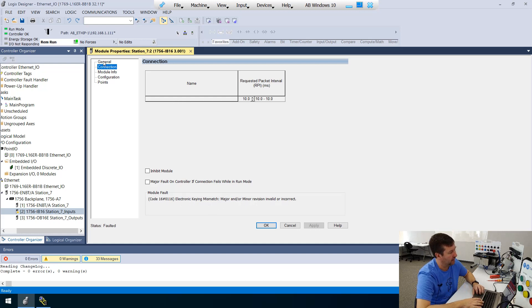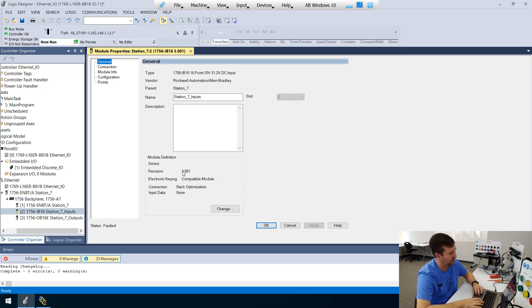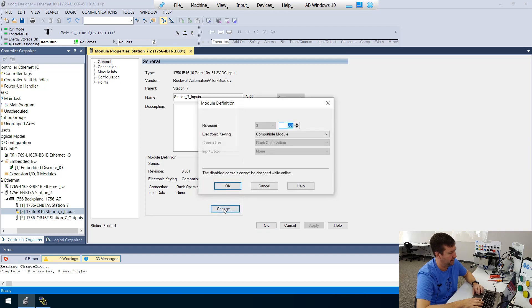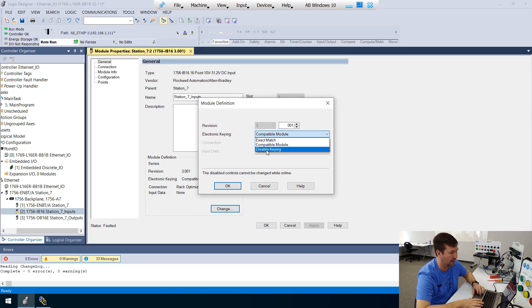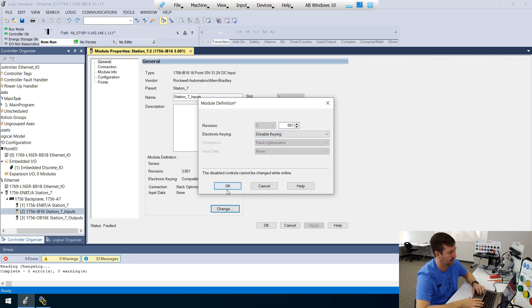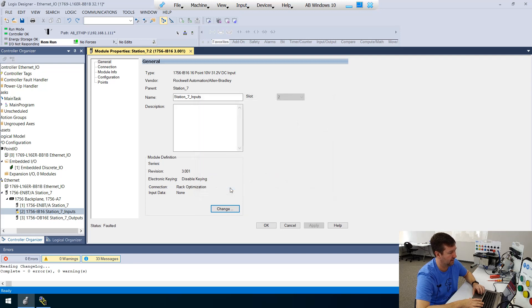then it's going to say electronic keying mismatch major or minor revision invalid or incorrect. So if I go back to general and change. Oh, okay. It's not going to allow me to change the revision while I'm online, but will allow me to disable the keying. So let's disable the keying.